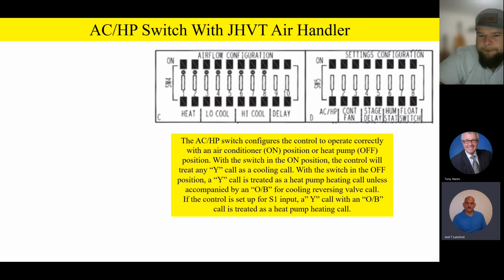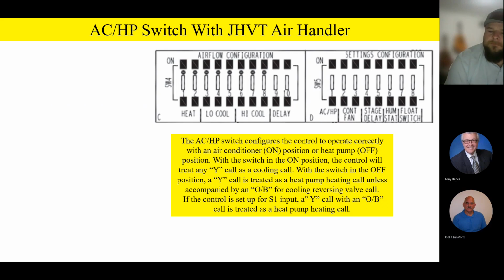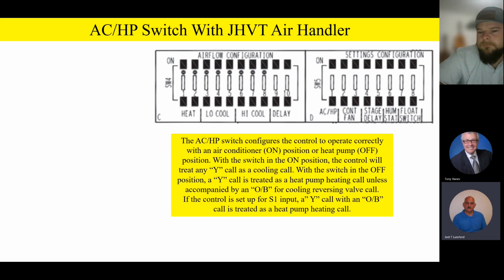So what I'm trying to say is, on just a plain Jane heat pump, when that switch is in the heat pump position and you get a Y call, it's a heating call. But if you have an OB selection with that, it becomes a cooling call on a regular heat pump. Now watch this. With that switch in the HP position, if the control is set up for that S1 input, you're telling the board, hey, I'm on an HMH7 outside, and now we're going to treat a Y call with a BO signal as a heating call. So it's exactly opposite of a regular heat pump. But I wanted to stress that whole scenario again.